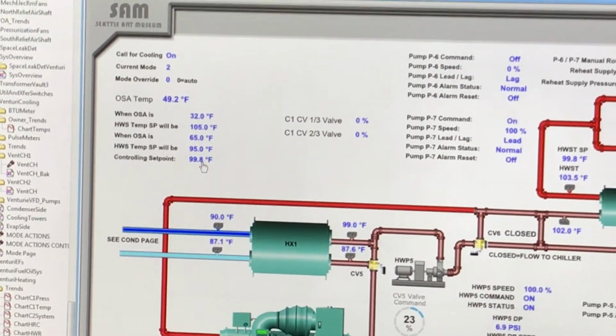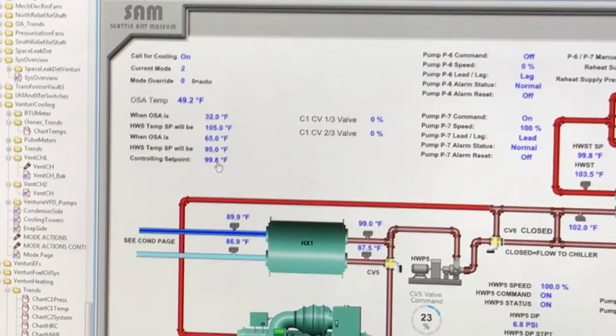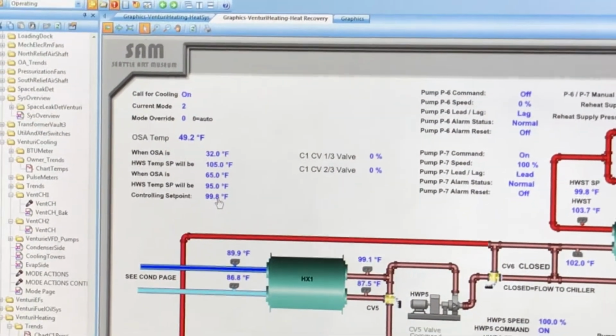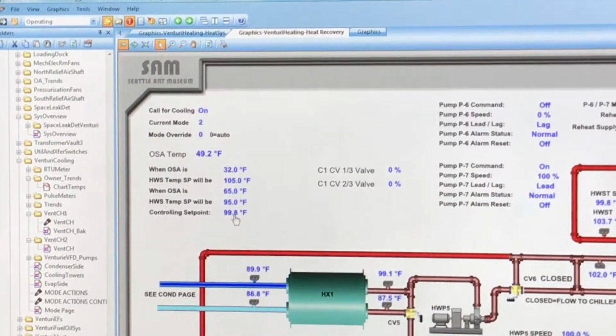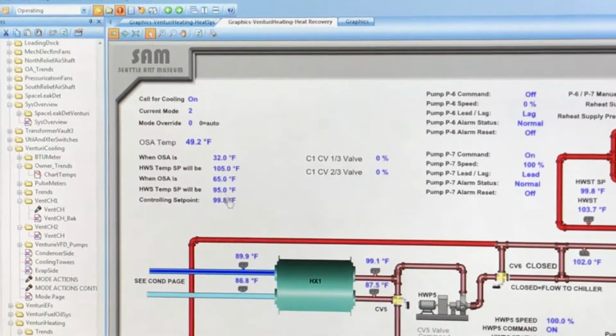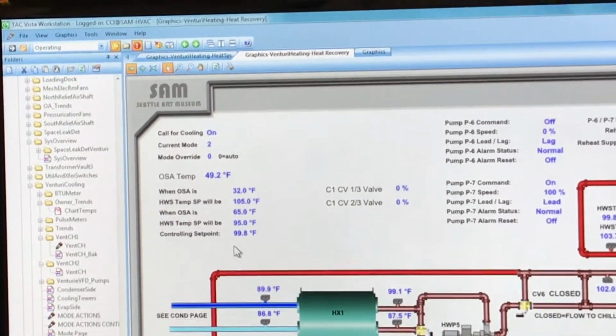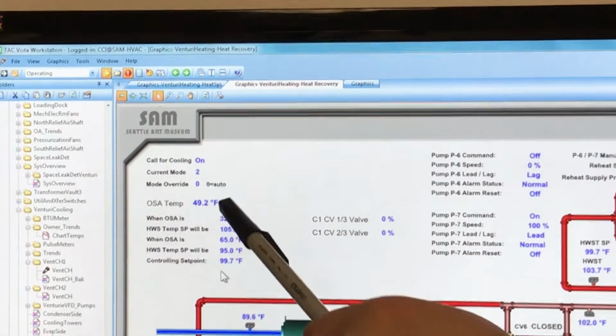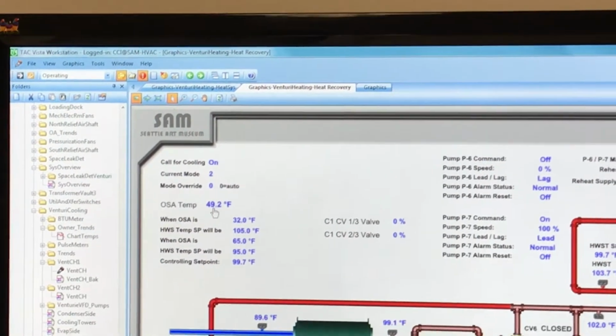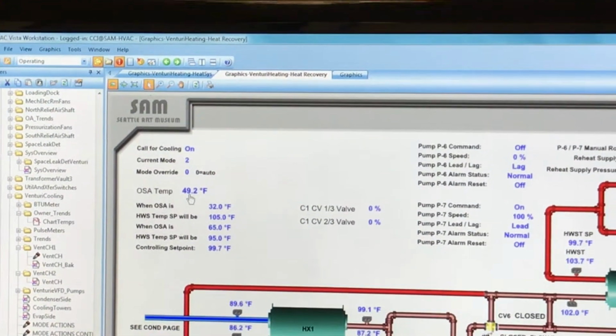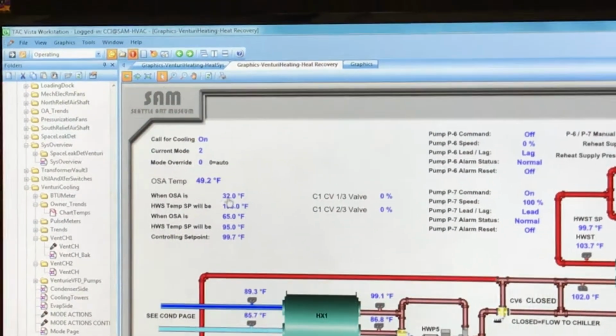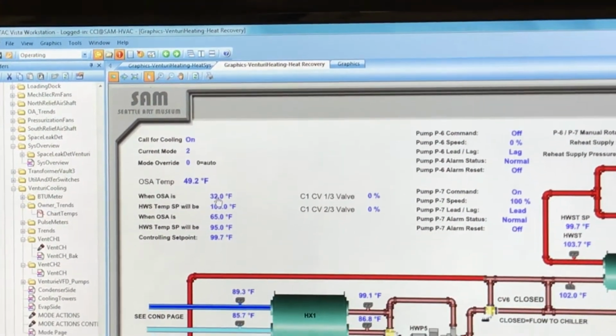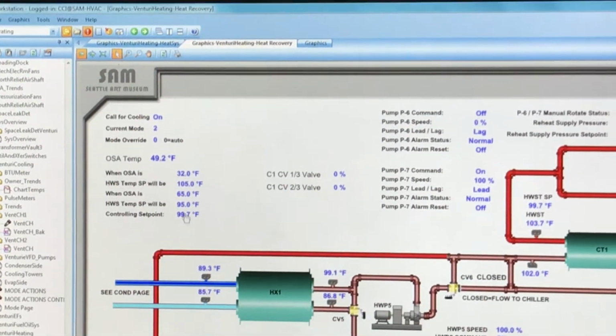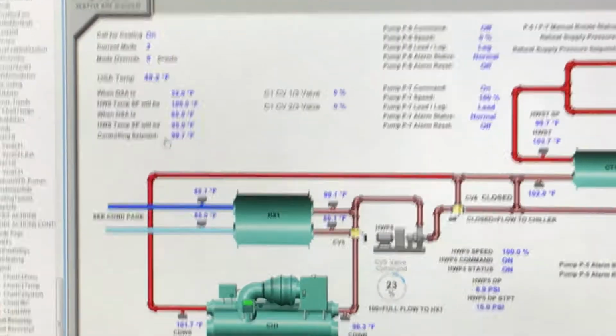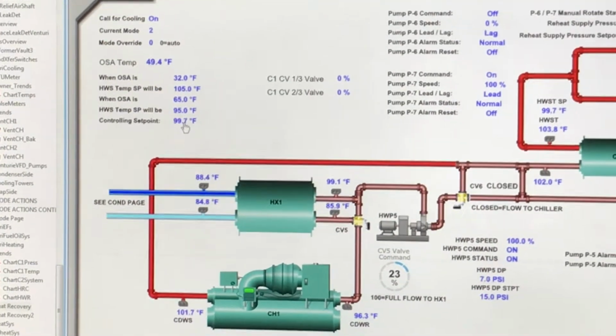Can you tell me why? Anybody? How come it's not 95? Or how come it's not 105? Because of the temperature outside. This setting is 49 degrees, and that tells me it's above 32 but less than 65, so it's going to be somewhere in the range of these two set points. Correct. And right now it calculates out to 99.7.